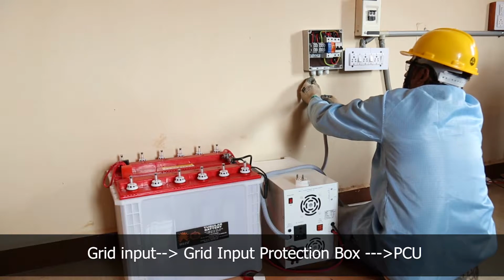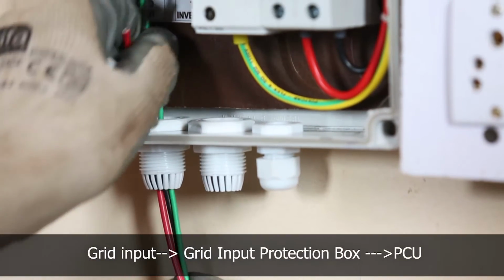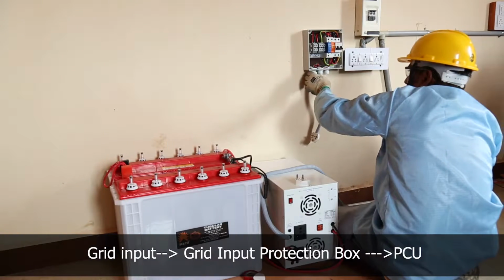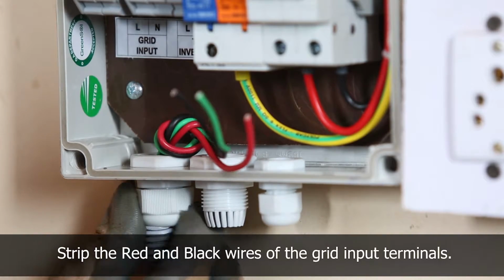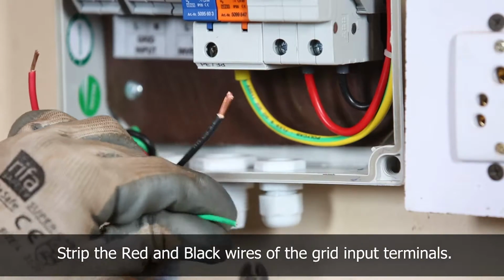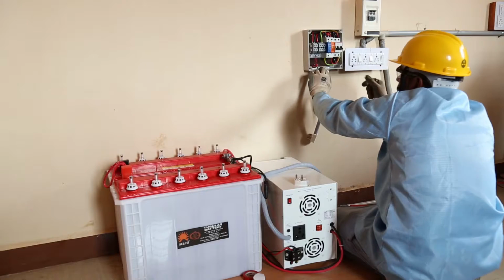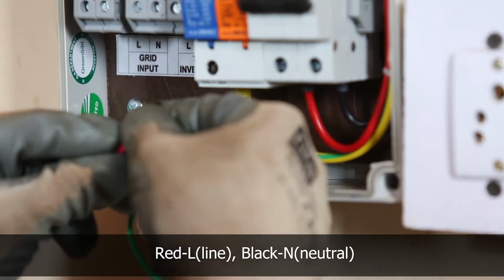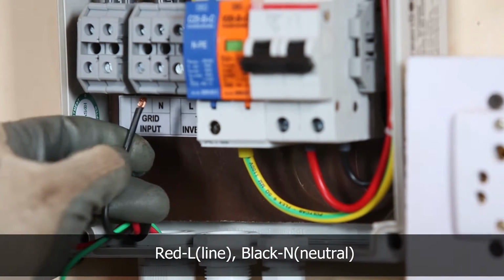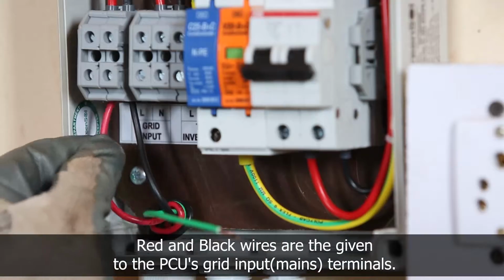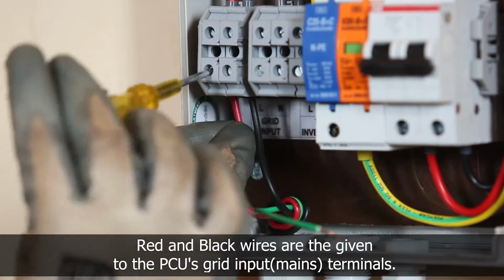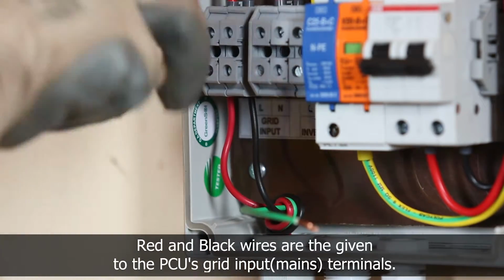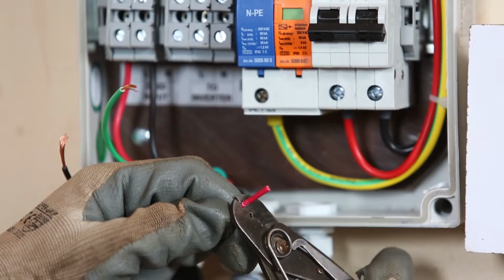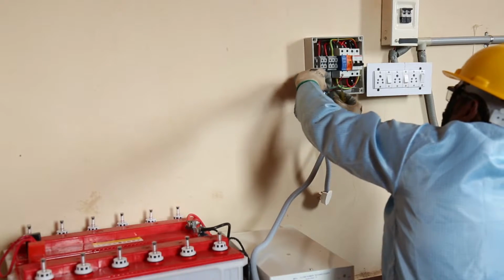Connect the grid to the input terminal of grid protection box and the output of the grid protection box to the power conditioning unit. Strip red and black wires connected to the input terminal of grid input protection box. Red wire is connected to the line terminal and the black wire is connected to the neutral terminal. Strip the next set of red and black wires and connect them to the output terminal of grid protection box.